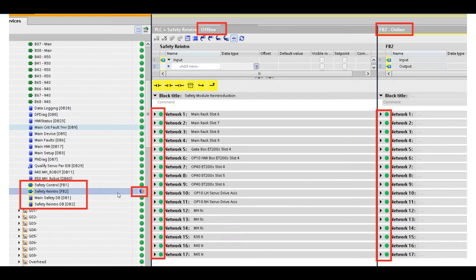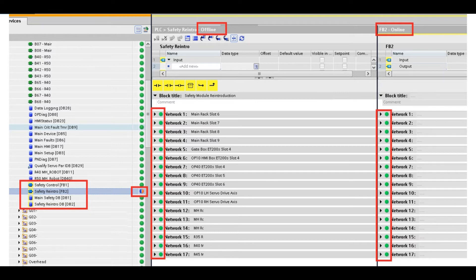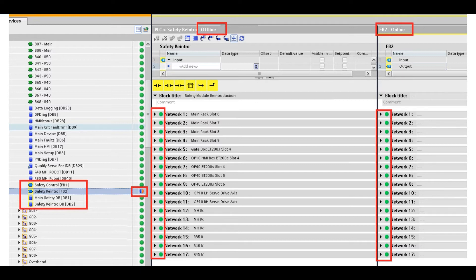As I mentioned, 100% you can guarantee you never touched the safety program before, touched the safety logic in this project before. I never logged in the safety administrator portion in this TIA Portal safety program. However, after I download the standard logic, I found the safety shows a difference.